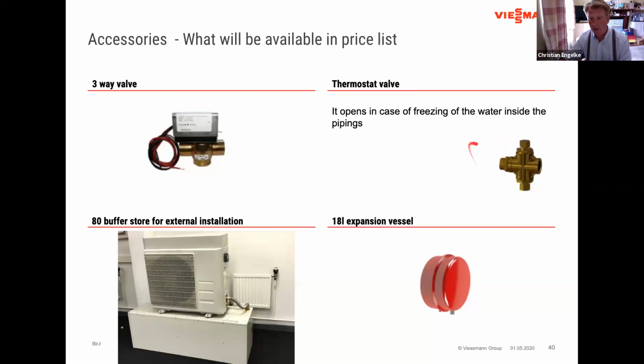So therefore we have an option for a thermostatic valve that's required if, for example, homeowners like to go on holiday over the winter period and switch all the heating off, which most people do in the winter. In case of potential freezing up of the outside unit and causing damage to the machine, because freezing water is expanding and then creating pipe bursts or other components bursting inside the machine, this is a thermostatic valve to allow expanding water to be drained to the outside. Well, as I said, it's an excellent optional extra. And then obviously other accessories like an expansion vessel or any other pipework you may require.